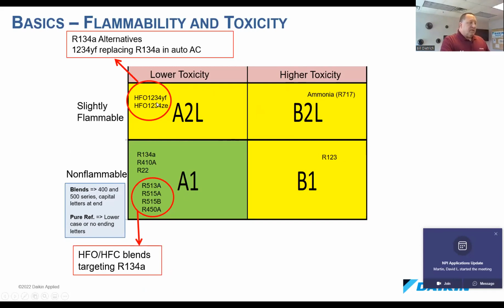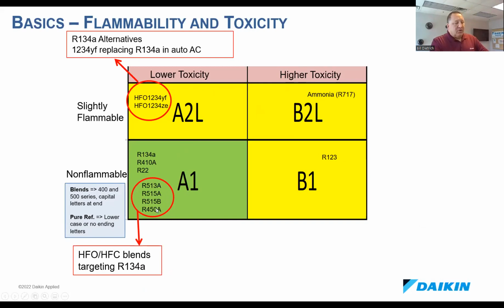And because of the 2L category, there's a bunch of blends that have been put together out there. And generally, these blends are designed to be close to 134A. And the basis for them is usually taking one of these two refrigerants and mixing something in it that isn't flammable to move it from the 2L box to the 1 box.